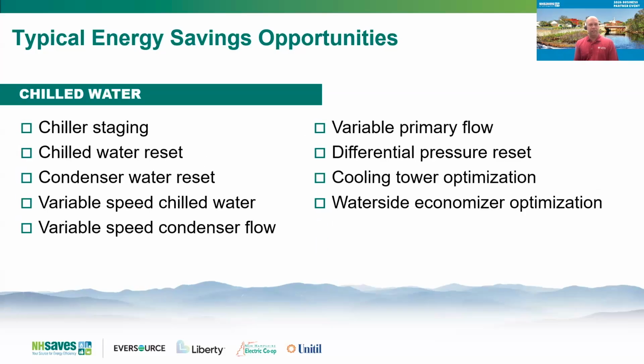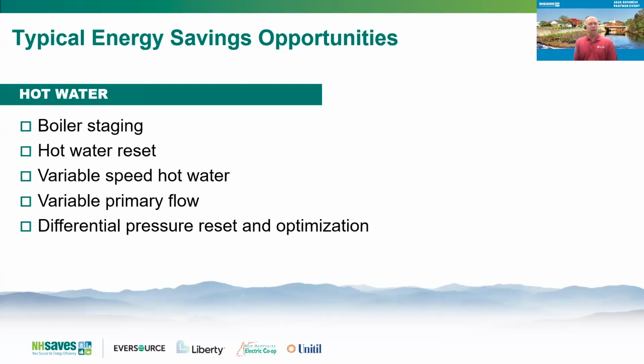On the chilled water side, chilled water reset and condenser water reset are pretty popular. Water side economizer optimization, a whole lot of opportunity around chilled water systems. Hot water systems tend to have fewer opportunities, but there's still boiler staging and variable speed hot water flow. Variable primary is one of my favorites. Just slow pumps down if they don't need to. If the flow exceeds the boiler's minimum flows, just slow the pumps down.